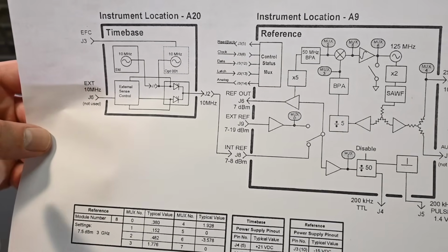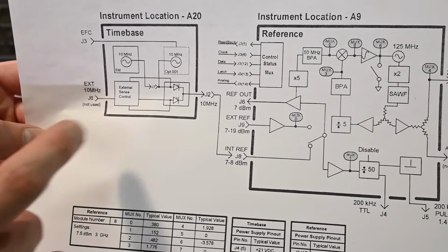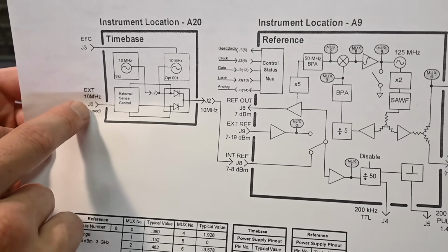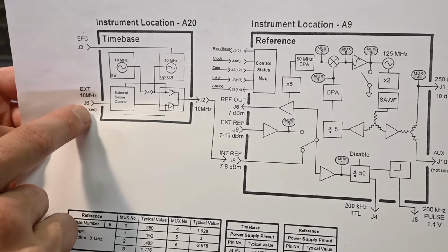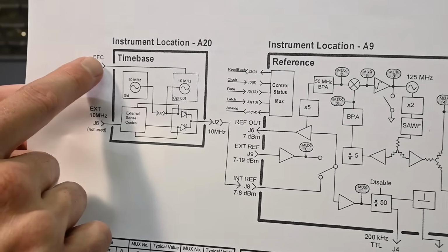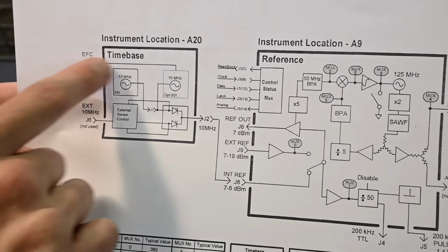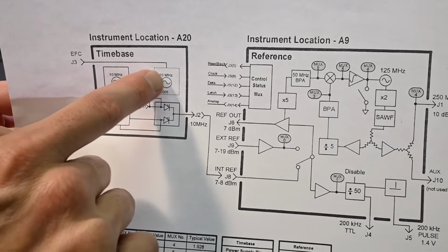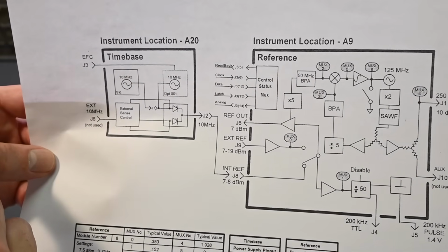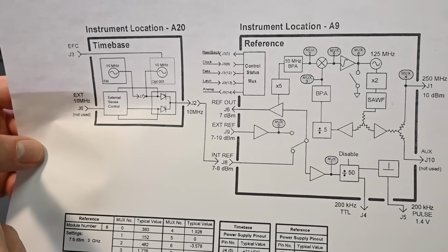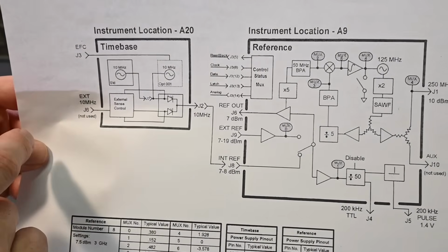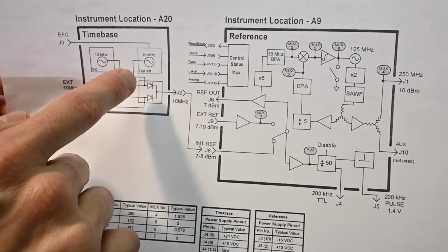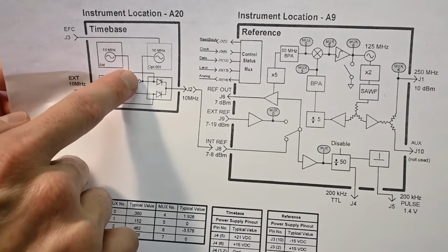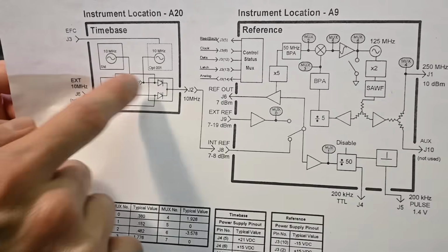So I'll take you down to the back panel connectors in just a moment. We'll look at all of this, but it's a little bit confusing because it says it's not used, but it seems like it is on this instrument. EFC is electronic frequency control. So you can electronically control the frequency of the reference oscillator, but that's not normally used. I'm not using it for the purposes how I have it connected, but that connector is on the back panel. So again, I'm not so sure that this is actually how the instrument works, with this sort of an internal connection. And if we take a look over here, something that I found in the service manual right here.